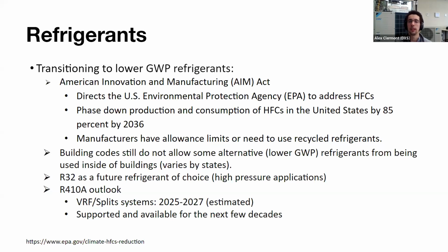Now, when you're trying to do heating, this is where high pressure refrigerants come into play and are really important. But currently, again, you cannot have R32 through occupied space, and it's going to be quite a few years before that's allowed at the federal level, and then a year or two to get adopted by the different states. Our estimate is that we're probably still 5 or 6 years away from seeing R32 in VRF systems and larger source heat pump systems. R32 has already started for small split systems for residential applications. And again, as I previously mentioned, air source heat pump chillers can transition quicker to this next generation refrigerant than VRF, as everything's centralized in the outdoor machine.